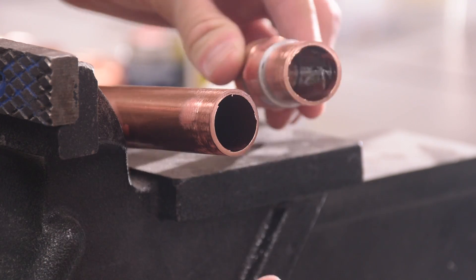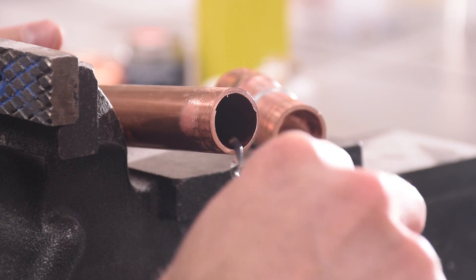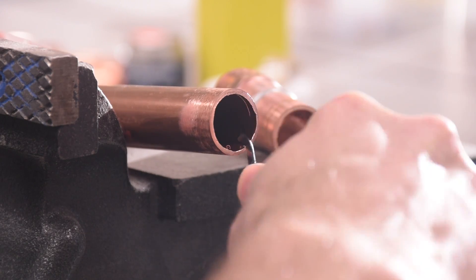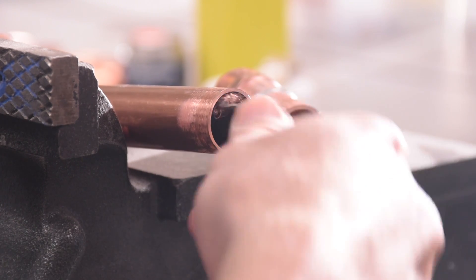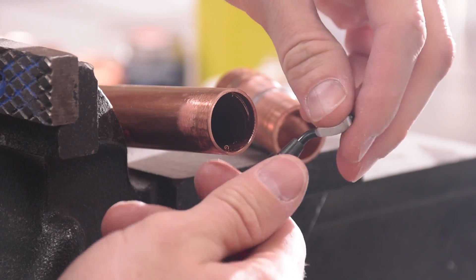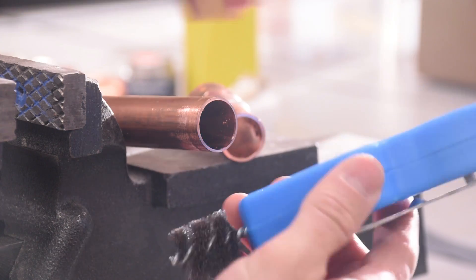So once you cut your tubing it'll have burrs inside that you'll need to get rid of. For that I like to use this style of deburring tool. It's got a hooked blade that you just run around the inside of a pipe a couple of times to smooth the edges. Your pipe brush might have a deburring plate like this one does and you could just use that to deburr as you brush your pipe. But I like the deburring tool better.